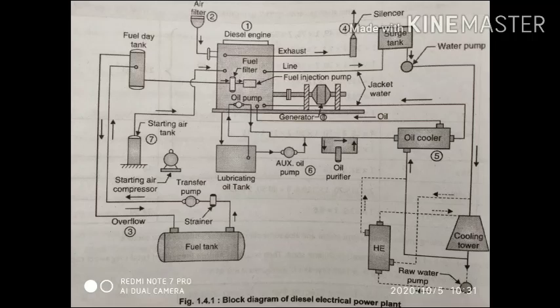As the temperature of exhaust gases is high, the heat of these gases is utilized in heating oil or air supplied to the system or to the engine. In case of a diesel electric generating unit installed in a steam power plant, the exhaust system also includes a water heater and steam boiler in order to utilize the heat of waste gases.